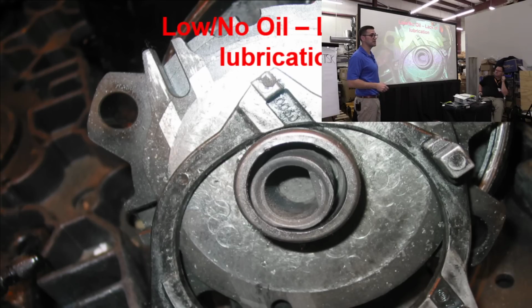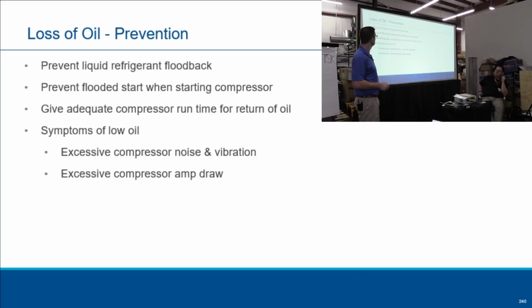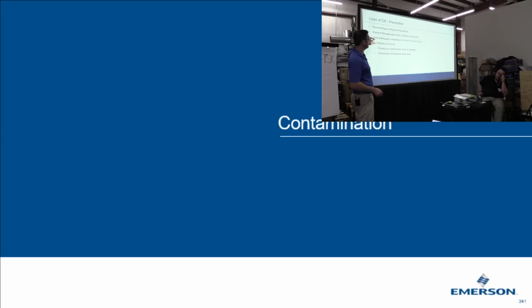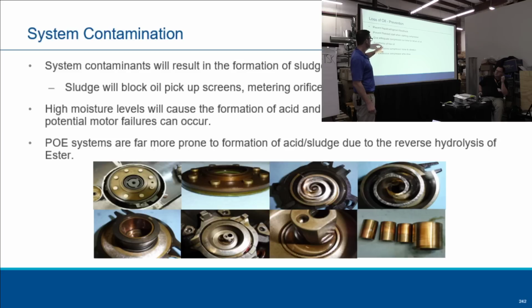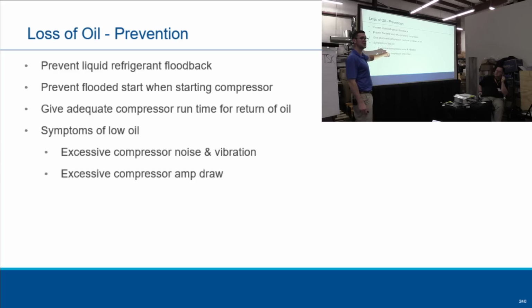Lack of lubrication. This is what it looks like. Scroll. Some more damage. Prevent liquid flood back. Prevent flooded starts when starting the compressor. Give adequate time to run the compressors, no short cycling. Symptoms of low oil: excessive compressor noise and vibration, and excessive compressor amp draw.